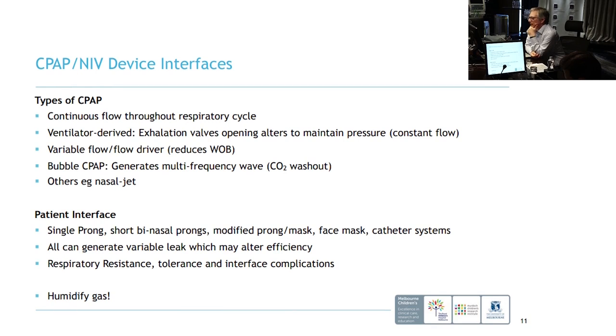Most of them are delivering essentially a continuous flow or a variable flow in most cases. Many of the ventilator-derived CPAP systems deliver a constant flow using an exhalation valve that opens or closes to maintain a constant pressure. And then you also have ones on the market which deliver a variable flow.